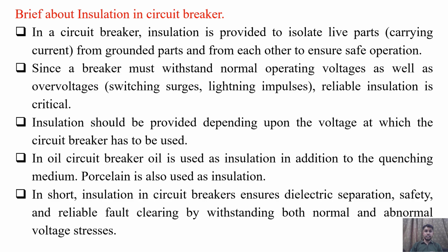Brief about insulation in circuit breaker. In a circuit breaker, insulation is provided to isolate live parts, that is the parts carrying current, from grounded parts and from each other to ensure safe operation. Since a breaker must withstand normal operating voltages as well as overvoltages due to switching surges or lightning impulses, reliable insulation is very critical. Insulation should be provided depending upon the voltage at which the circuit breaker has to be used.